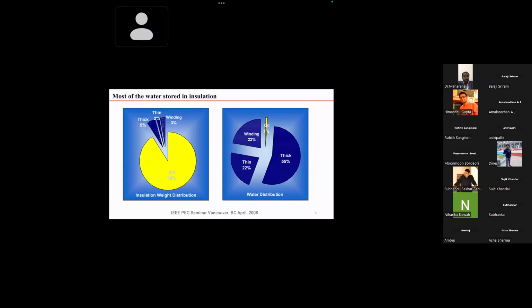Thick I consider as press board, and thin we can consider as kraft paper, for those who know about transformers. The winding is covered with kraft paper, and an insulation barrier is created using press board, which is a bit thicker. For water distribution: the thick part takes 55% weight, the thin part takes 22%, winding also carries 22% weight, and the oil has only 1% of the weight.